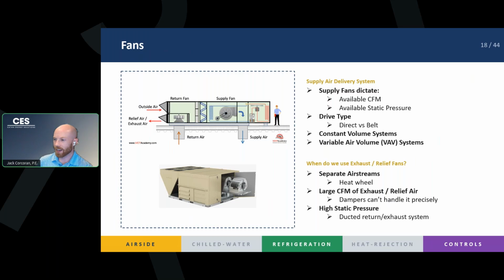And the last thing that your airflow sees before it leaves the unit is the fan, right? The supply fan pulls your air through the unit and then pushes it out into the space, right? So your fans are very important. They're going to dictate the amount of CFM that you have available. Larger fan, more CFM. It's also going to dictate the static pressure, right? More horsepower, more static, more CFM. The bigger the fan, the bigger the blades, the more you can get out of it, right? And so the supply fan is a very important piece of your rooftop unit, and it is driving your airside loop throughout the rest of the building.